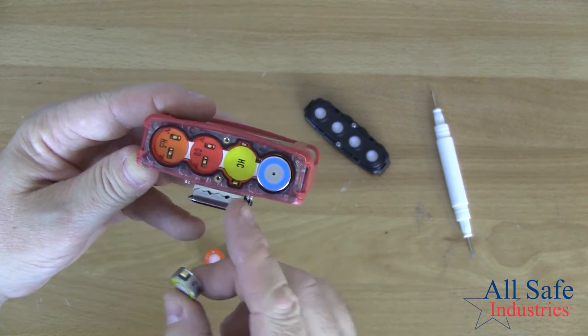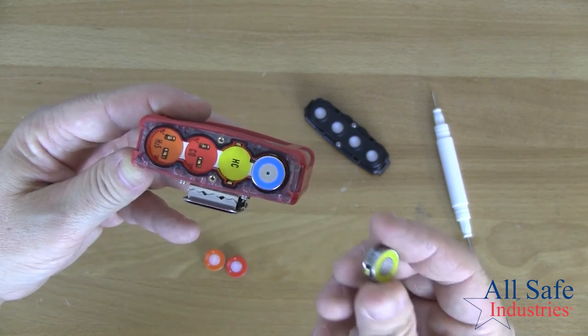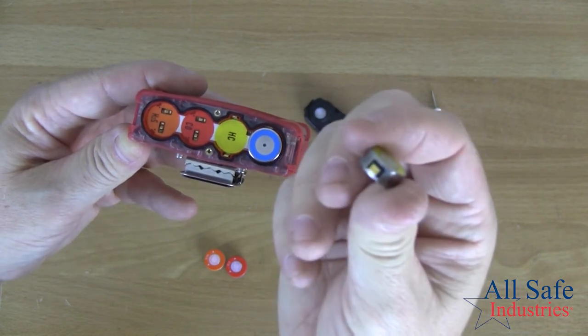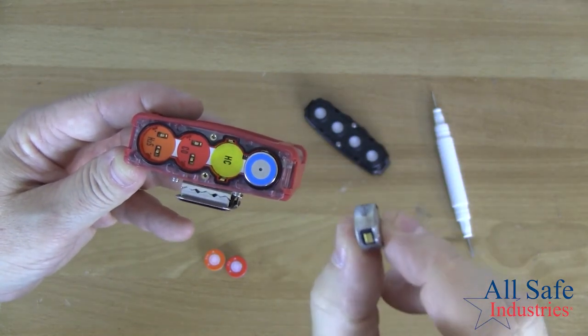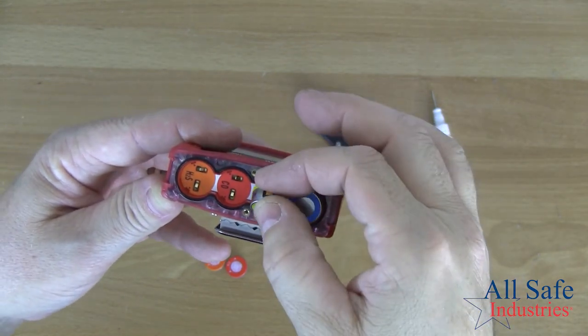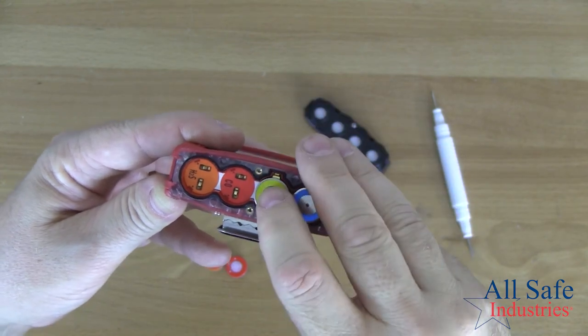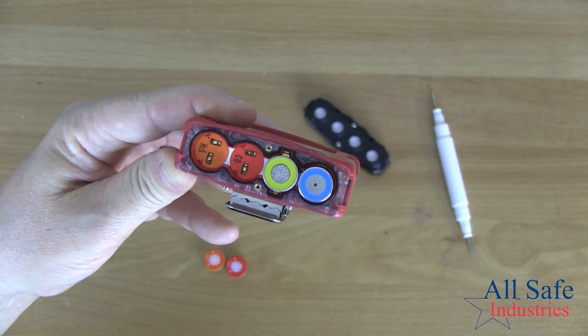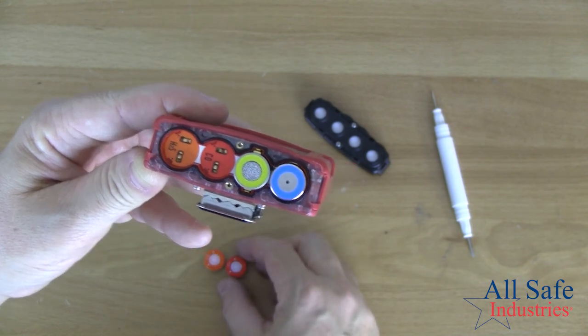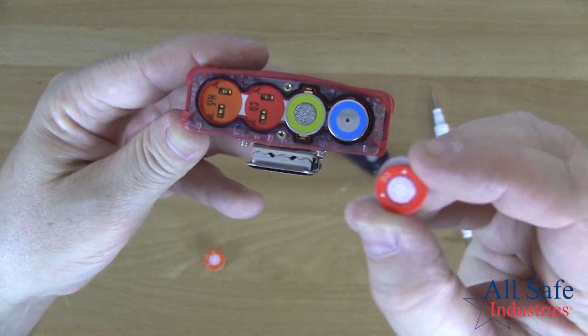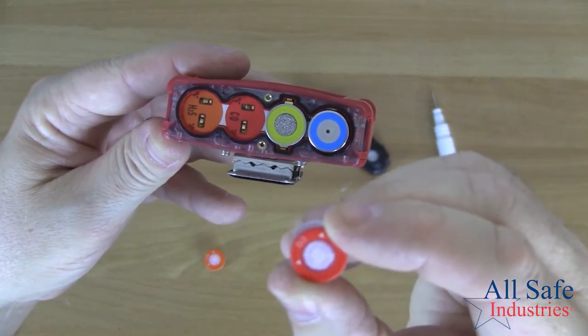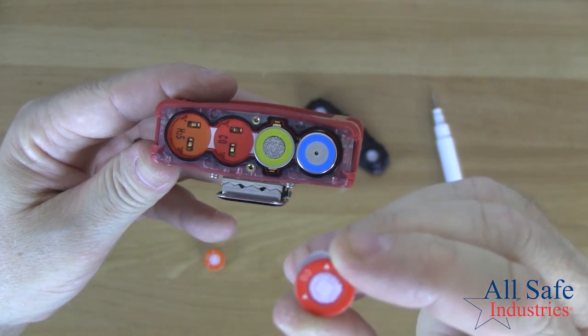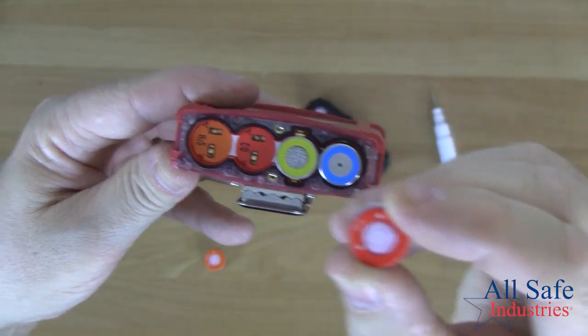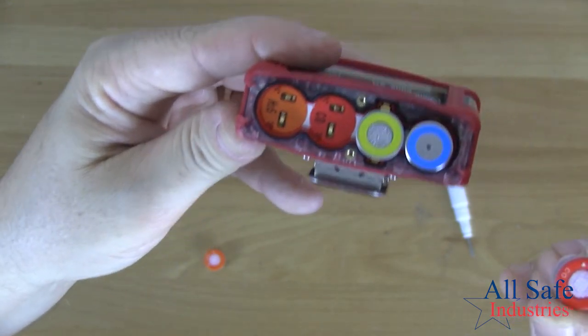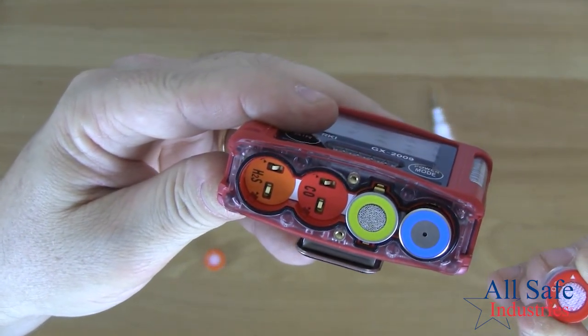Your hydrocarbon is what HC stands for. It's your LEL sensor. The contact pins are on either side of the sensor. And so you want to make sure that when you install that, those contact pins match up with the contact pins in the instrument. And then if you look at the CO and the H2S sensors, they have little arrows on the top of them. And you want the little arrows on the top of the sensor to match up with the arrows on the sensor position inside the instrument.